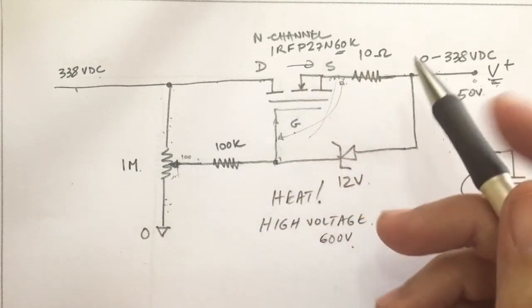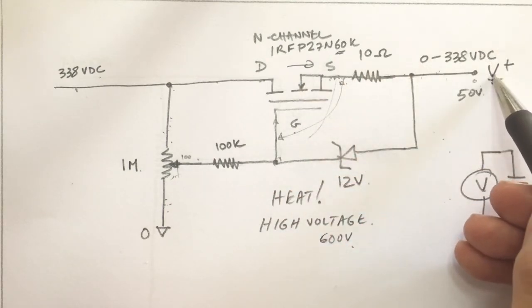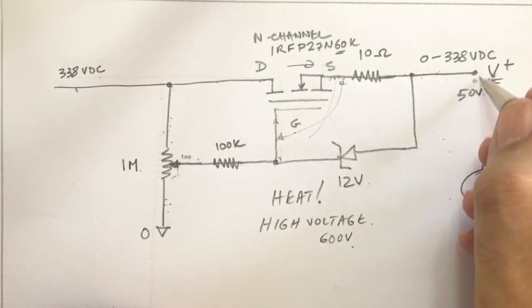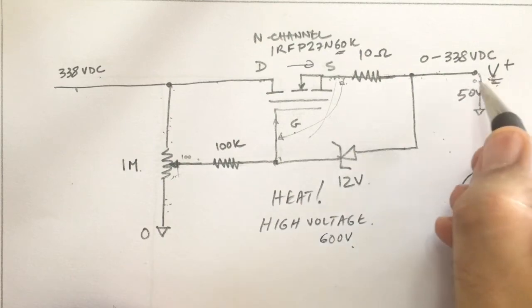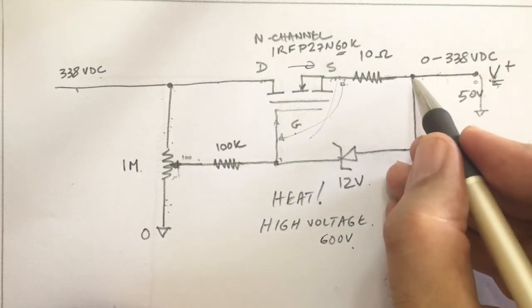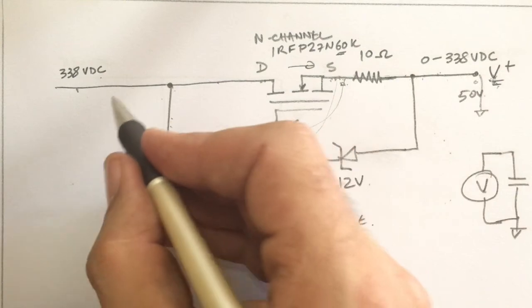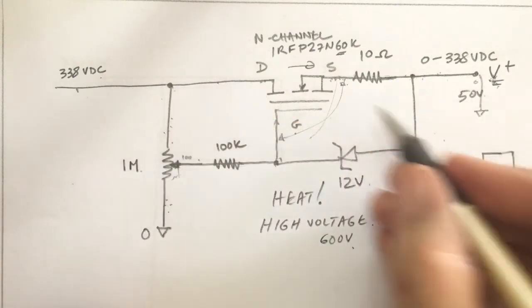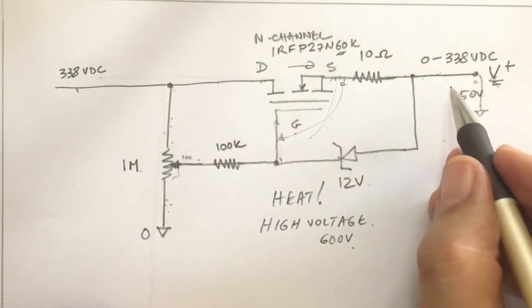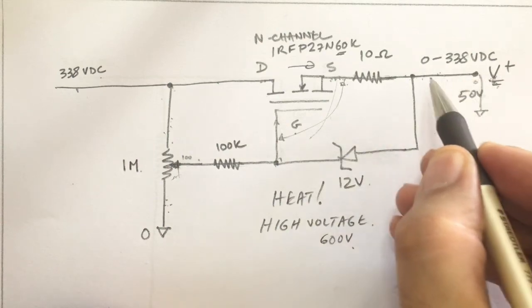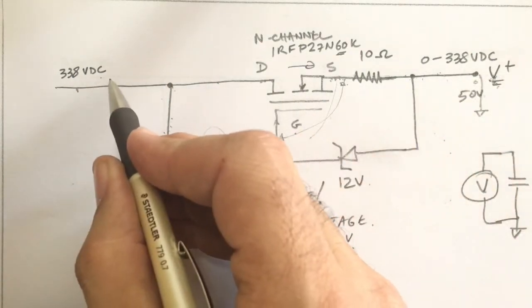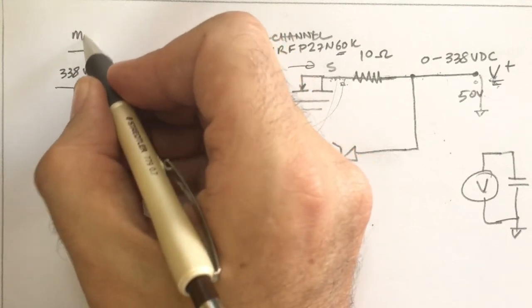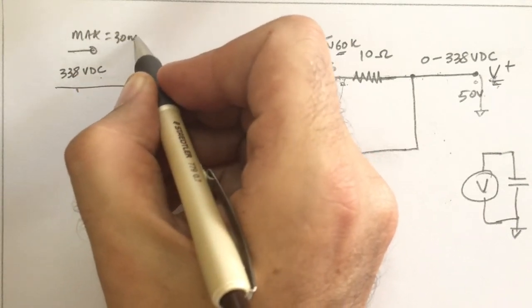As you'll see, we take this V+ and minimize the maximum current. Assume there's a short on here, shorted to ground—what do we need to do to reduce this current? A, to protect our MOSFET; B, to protect our transformer; and C, to protect any measuring equipment in between. The thing to do is define the maximum current coming out of the transformer as approximately 30 milliamps.